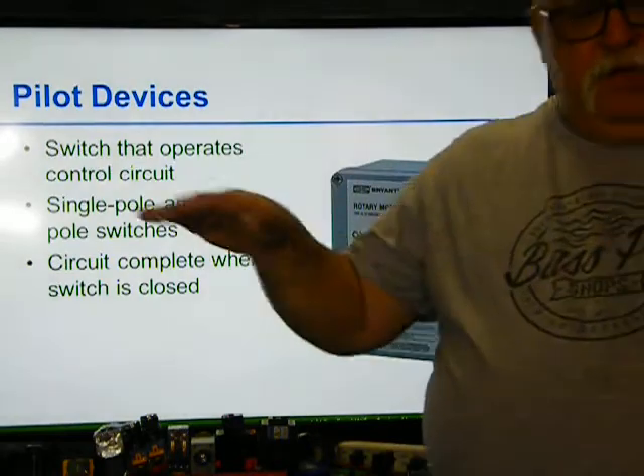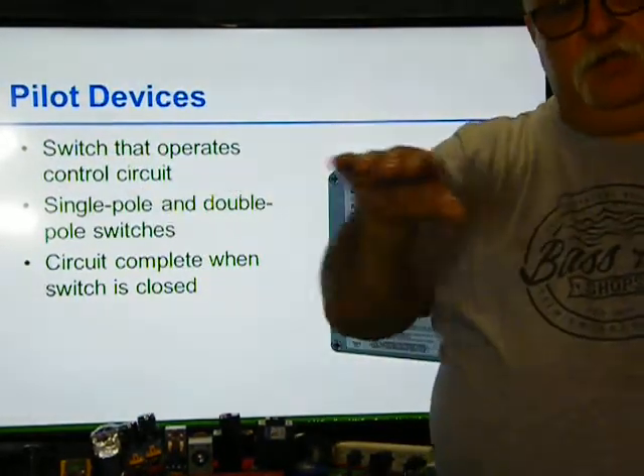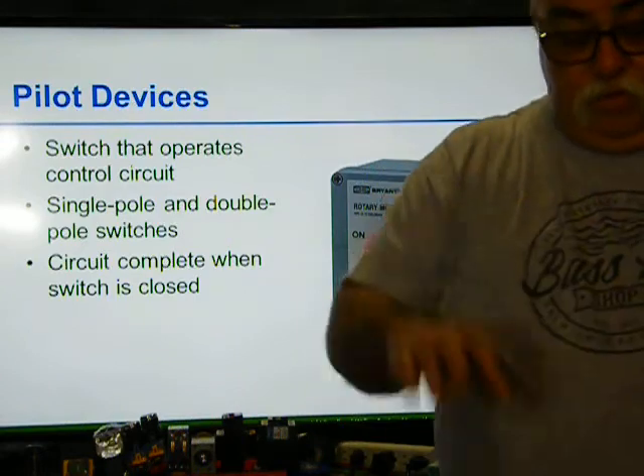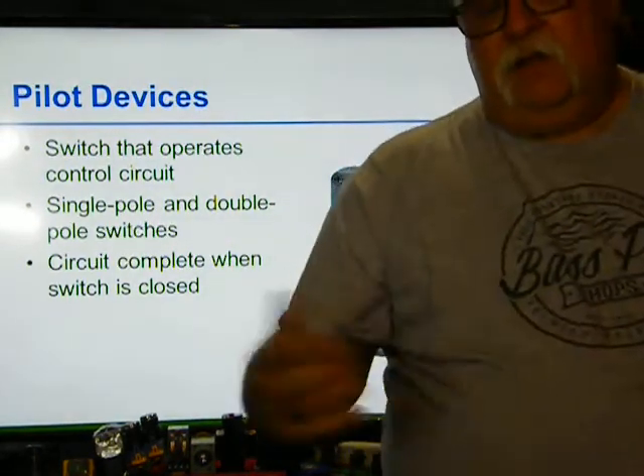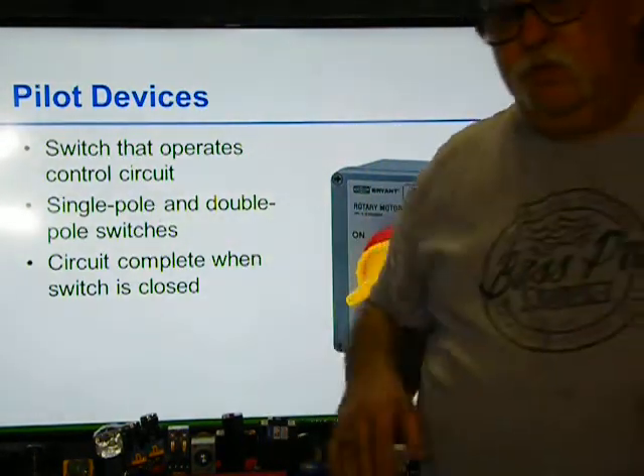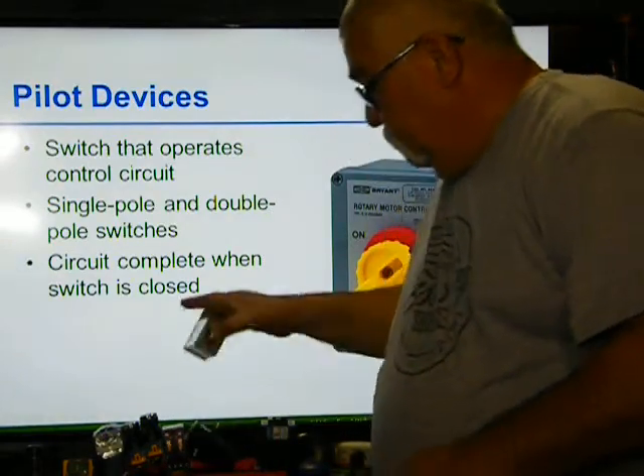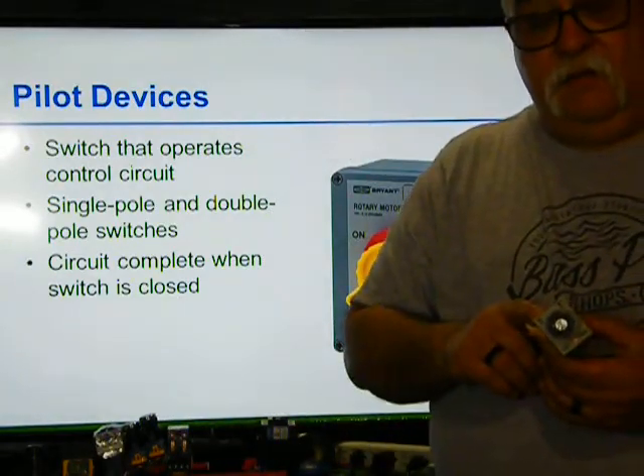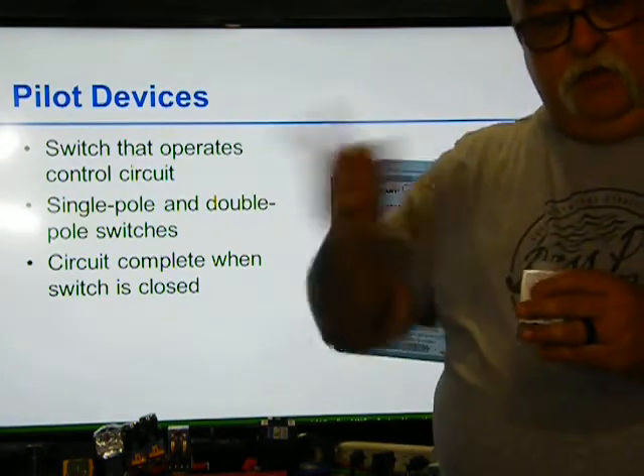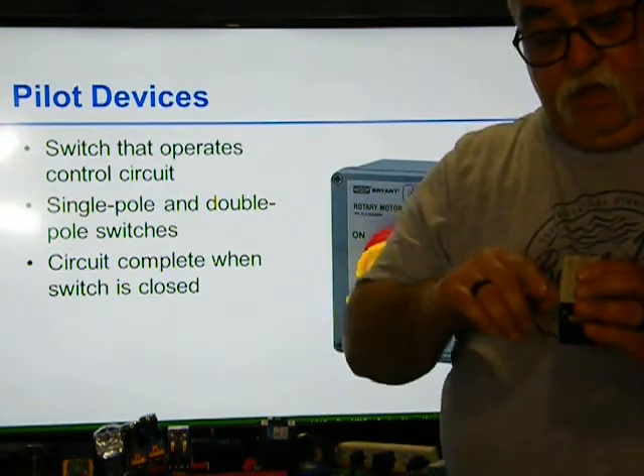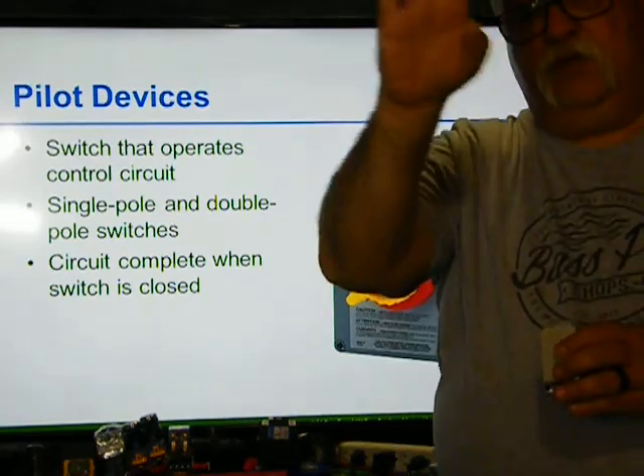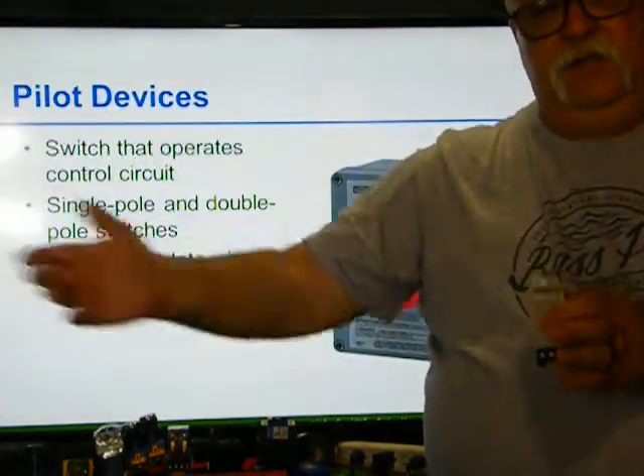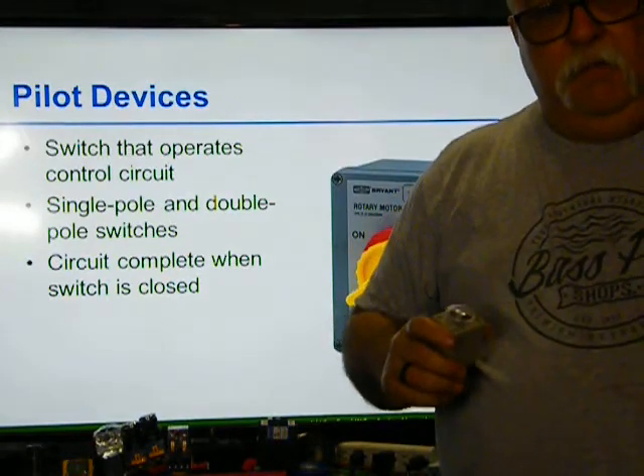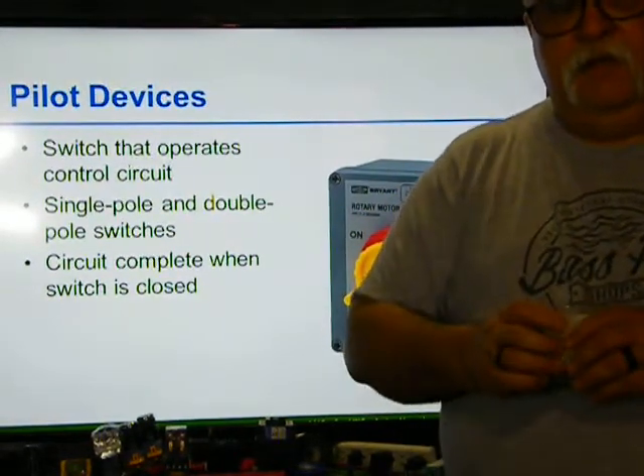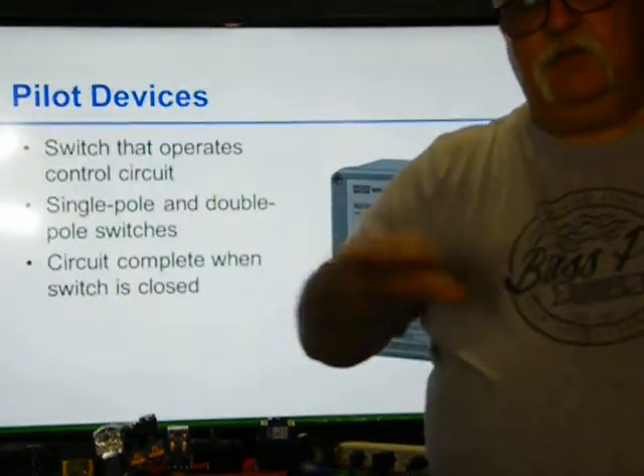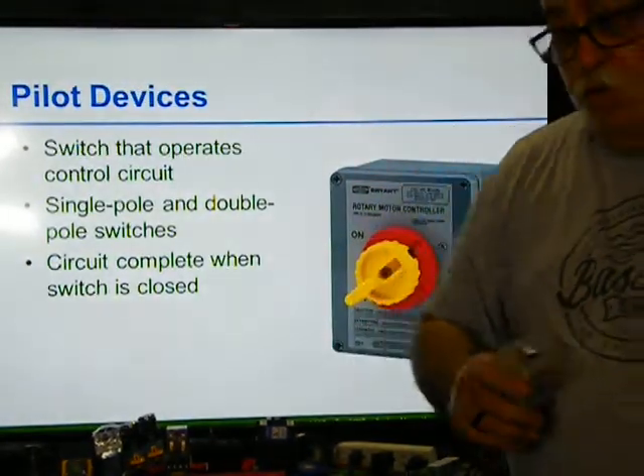Okay, so a limit switch, you have a conveyor belt and it's moving, and you want it to stop at a certain point. You know, so I'm working, assembling something, and I got 3 minutes to assemble it. So the limit switch moves over, hits the limit switch, and it goes to a timer relay, and it sets a relay. So all of a sudden, okay, turn on. But this relay, you got it set at 3 minutes, so all of a sudden it goes till it gets to 3 minutes. Once it gets 3 minutes, now it moves again till it gets the next bump on the conveyor belt, and it hits that limit switch and it stops. So the limit, it allows something to move. The limit, it only limits it. So that's one way.